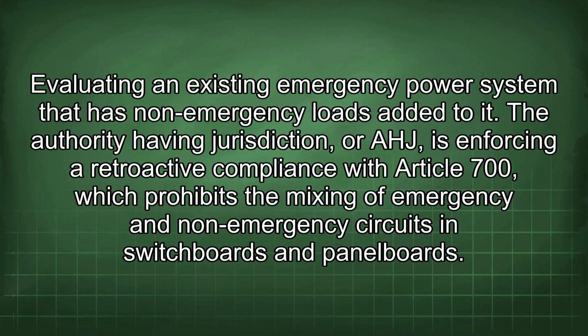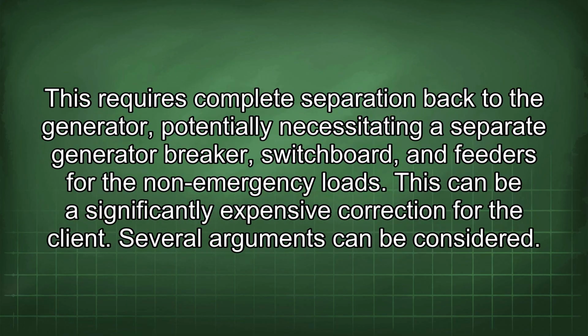Evaluating an existing emergency power system that has non-emergency loads added to it. The authority having jurisdiction, or AHJ, is enforcing a retroactive compliance with Article 700, which prohibits the mixing of emergency and non-emergency circuits in switchboards and panel boards. This requires complete separation back to the generator, potentially necessitating a separate generator breaker, switchboard, and feeders for the non-emergency loads. This can be a significantly expensive correction for the client.